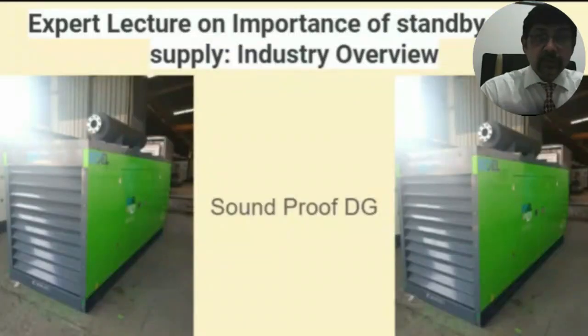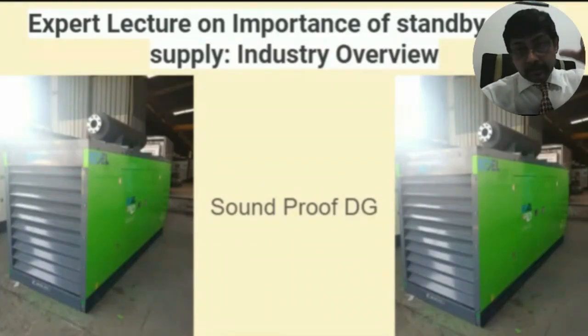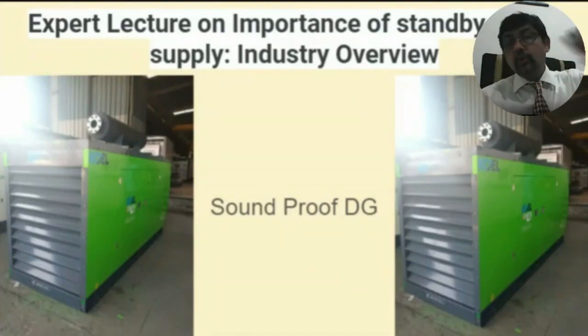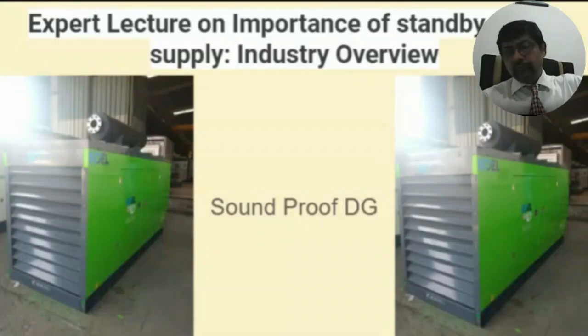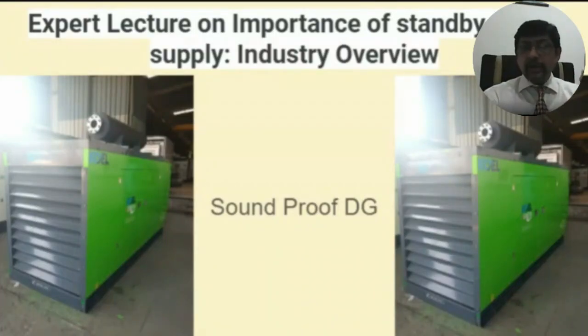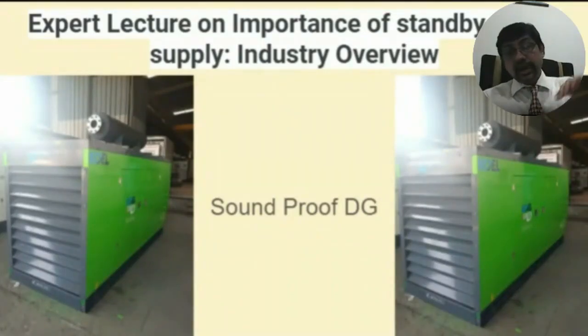Yeah, next. Now, this is the soundproof generator. Again, with the louvers of the exhaust, radiator, which we can see here, and a silencer on the top. We are seeing the flange there in front of the black silencer, the silver color. That's a flange. And from there, it is connected and taken outside the room, or maybe a spout kind of a thing, taken for half a meter or 1 meter, so that it is dissipated in the air. But these do not require any special exhaust chimneys, because these generators are all below 1000 kVA. The Supreme Court has said any generator which is above 1000 kVA will have to have 30 meters of chimney height. That is, the exhaust coming out of the generator has to be released high up in the air, 30 meters above the ground level.